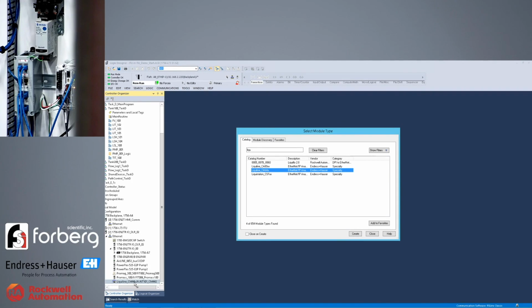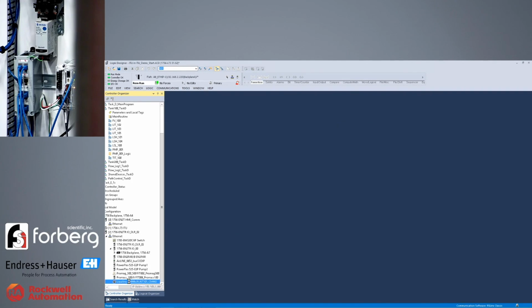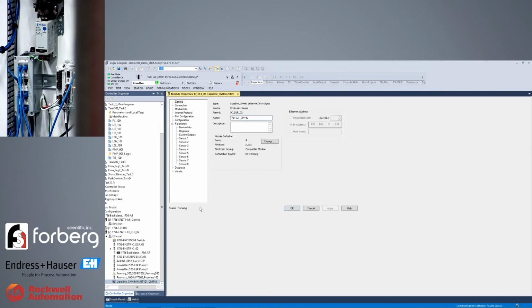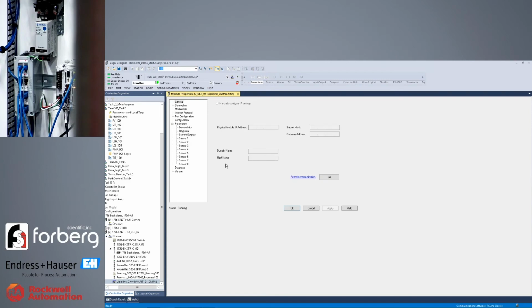And as I reopen the add-on profile, you'll notice things like, first of all, when I actually created it, I did not need to know the I/O connection size or the data types because all that work has been done for me, and I didn't need to use a generic Ethernet profile. I used the specific one for this device. So I'm going to step through some of the tabs. I'll start with the Internet Protocol tab. And what you'll notice on here is from the physical device, it picked up the subnet mask and the gateway address.